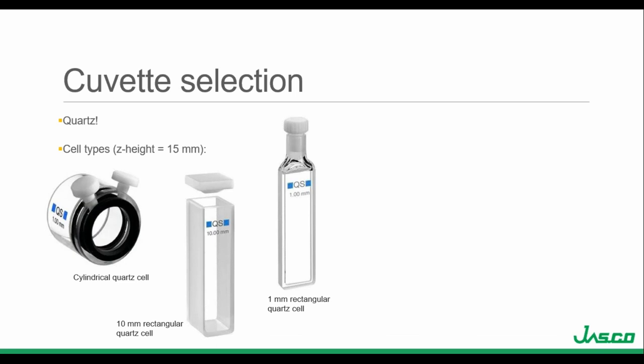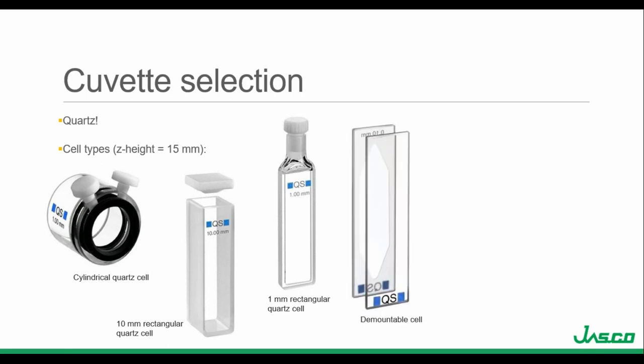Aside from path length selection, the cuvette material and volume are also important parameters for circular dichroism experiments. Quartz cuvettes are necessary for CD measurements due to their transparency in the far UV and because they typically have little to no birefringence, which can lead to artifacts. The standard cuvette has either a 1mm or 10mm path length and can be rectangular or cylindrical. Demountable cells are used when shorter path lengths are beneficial for reducing overall absorbance. They hold smaller volumes but can't be used for temperature-dependent studies because they're not completely sealed.